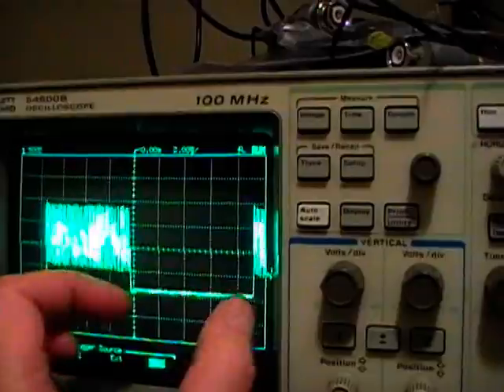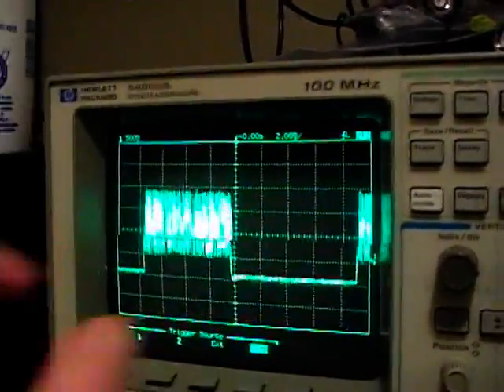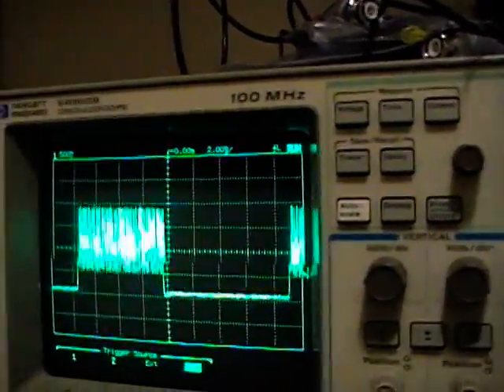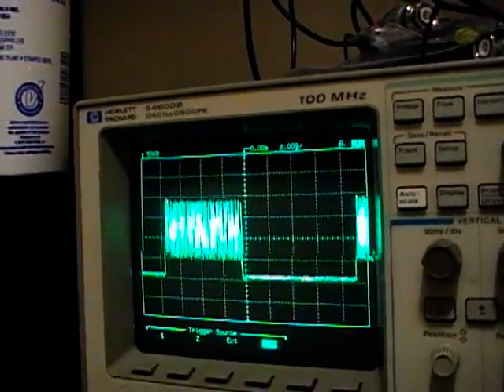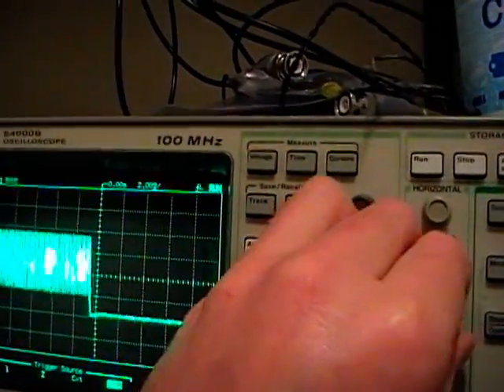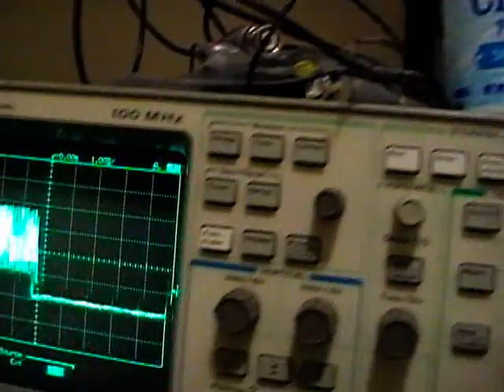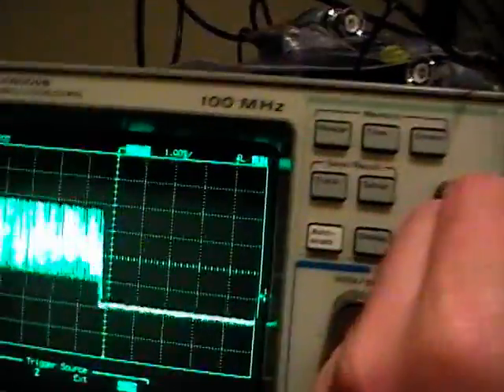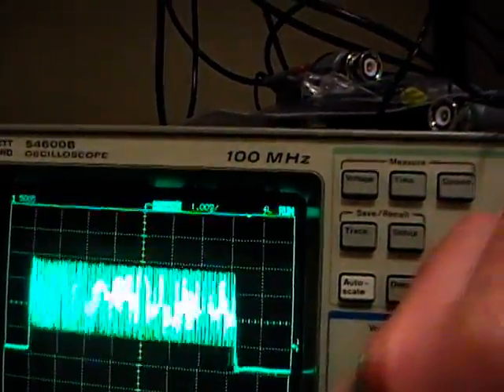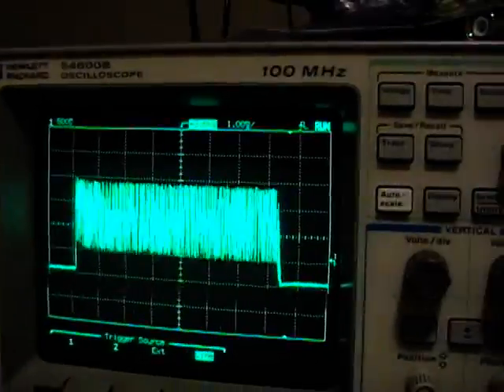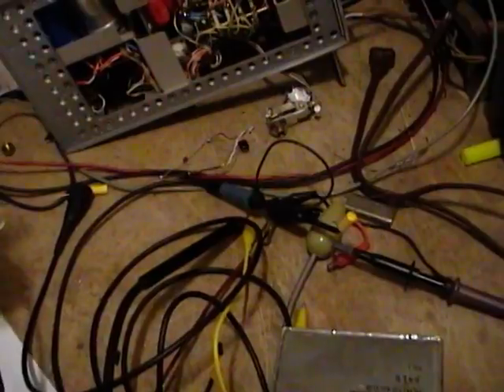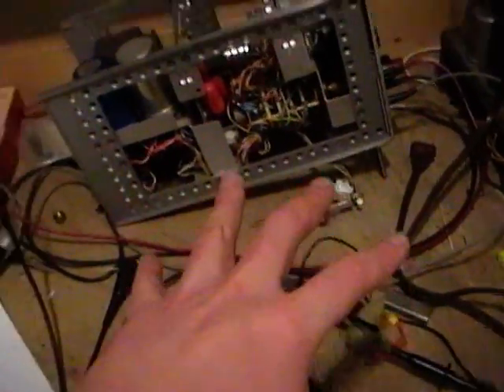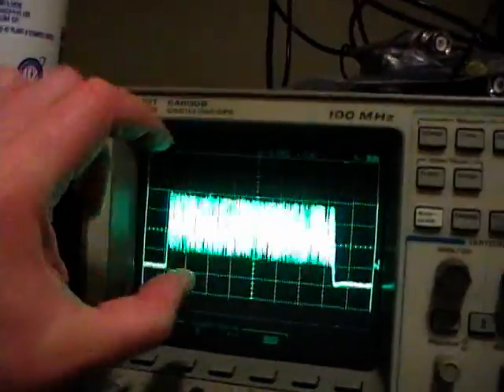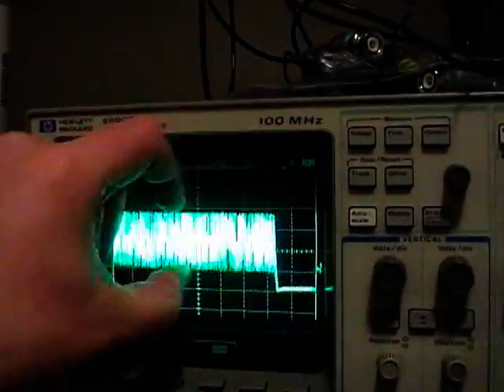The reason they put this blanking in there is to make it a little bit easier for your scope to figure out what's going on and to lock into that signal and give you a stable picture. Ideally you'll have a scope that has a delay on it, so you can lock to the line, and then you can use this control to scooch it over so you can see the whole thing and fill up as much of the screen as possible. So in this case, all I'm doing is the sweep generator is going right to my scope. There's no radio in between or any device I'm analyzing. So you're going to get the same amplitude all the way across the board.